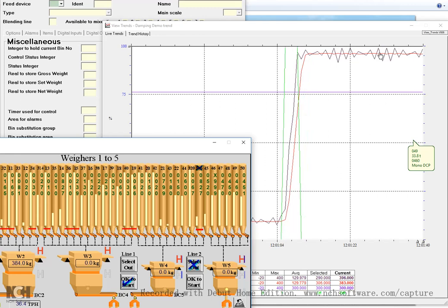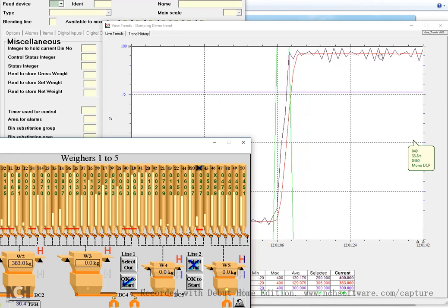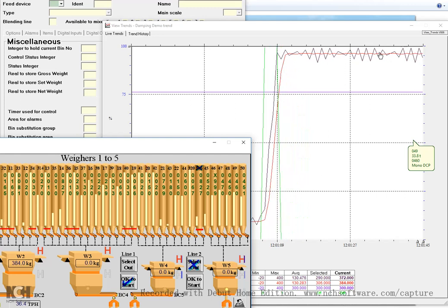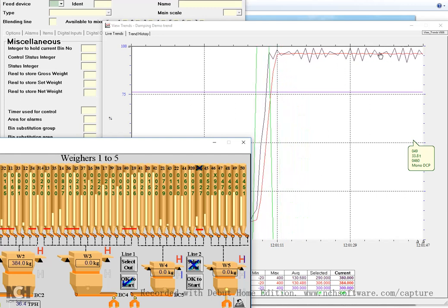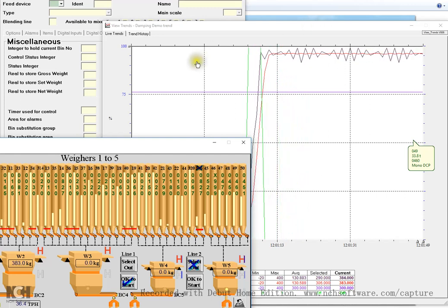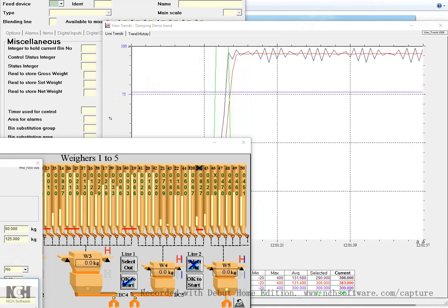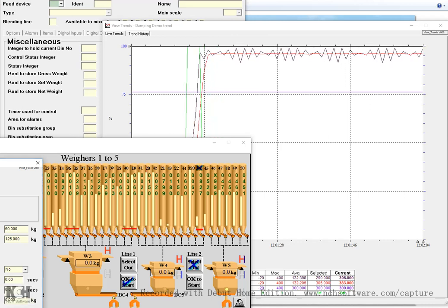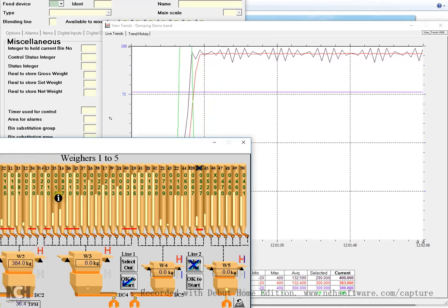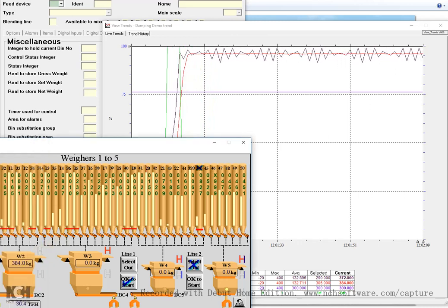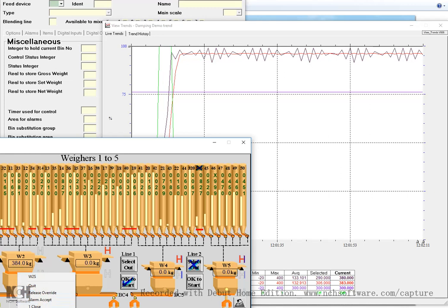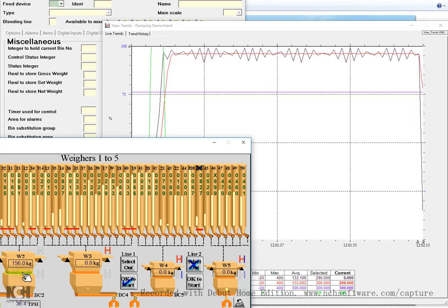If you have auto compensation selected in, the system will automatically learn the new in-flight compensation value over the next 5 or 6 batches. So for this tutorial, I'm going to manually change the in-flight compensation to something more appropriate. In this case, it's 125 kilograms.